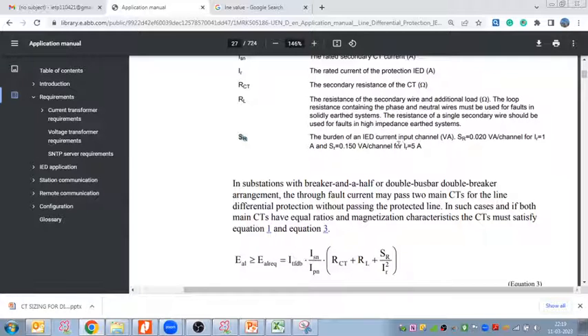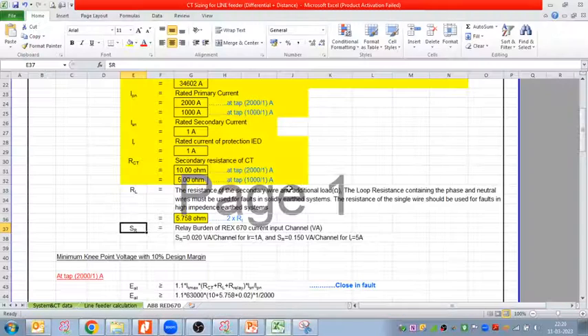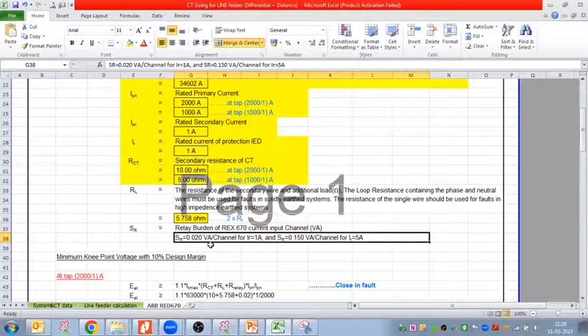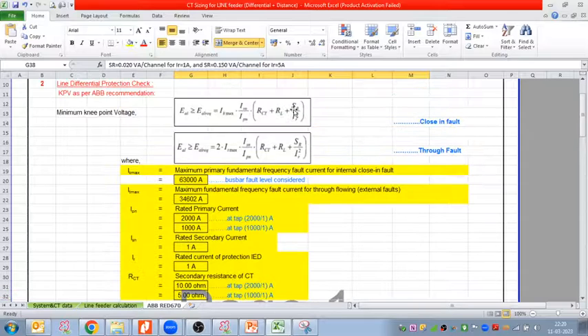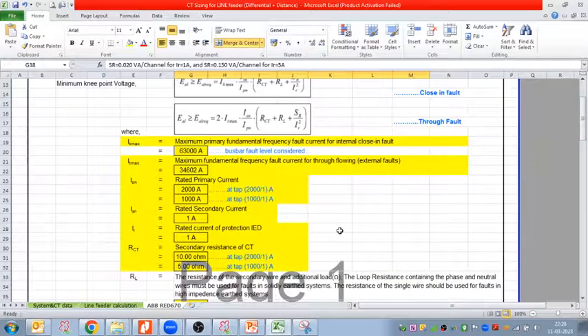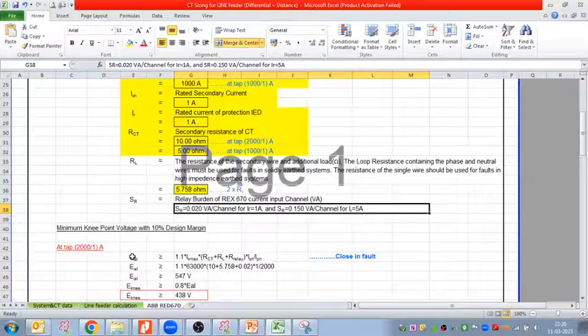So the burden of the IED current input channel, SR would be 0.020 VA per channel for IR 1 ampere. If your relay current is 1 ampere, then the SR would be 0.020 VA. So that we are putting in this calculation, 0.02 VA. The SR, this SR here. Okay, SR here 0.020.